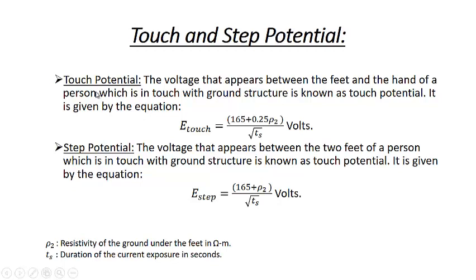The touch potential that appears between the feet and the hand of a person should be such that, keeping in mind the resistance of the human body, when you divide the touch potential by the resistance, the current that will flow through the human body should be less than the let-go current, or even lesser than that. So we need to design the ground structure in such a way that touch potential and step potential both will produce a current flowing through the human body that is less than the dangerous value.